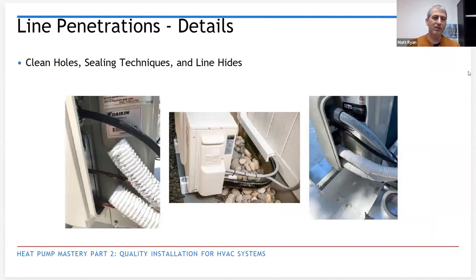I've got some examples of line sets, protection and sealing. The one on the left there, you can see some exposed copper. That's kind of a big no-no. You lose a lot of efficiency through that exposed copper. That's what I try to hammer home here: you should see no copper or brass. It should be indoor to outdoor, completely insulated and sealed up. Summertime, they'll sweat a lot. You'll get a lot of condensate on those lines. And in the wintertime, you're just losing performance.